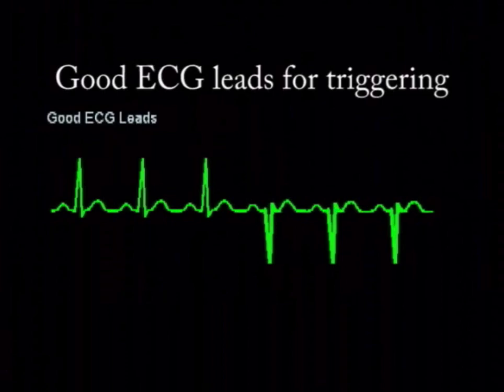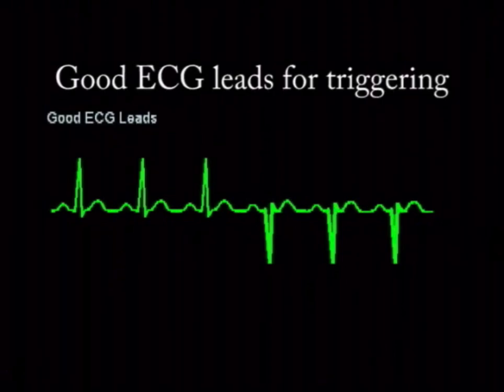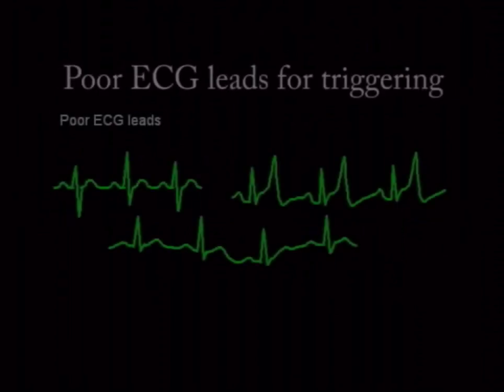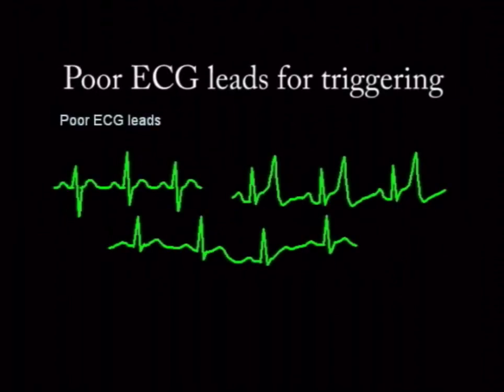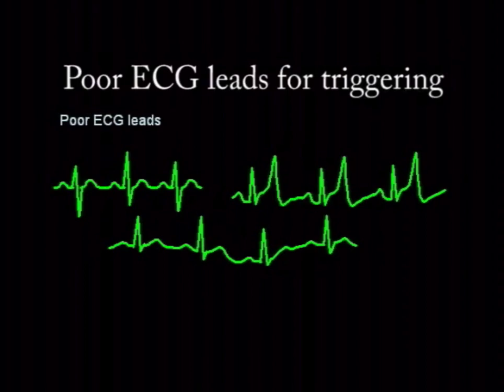As required with all ECG monitoring devices, it is important when applying the ECG electrodes to verify good skin contact and clean signals. Leads with unidirectional QRS complexes are generally the best choice for consistent triggering. Avoid biphasic QRS complex leads, leads with tall P or T waves, leads with wandering baselines, or leads with artifact whenever possible, as these may cause triggering issues.